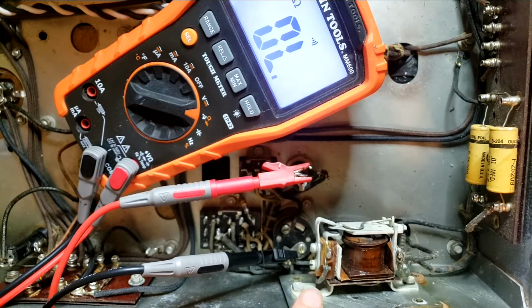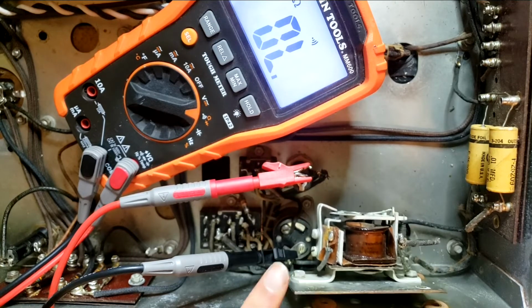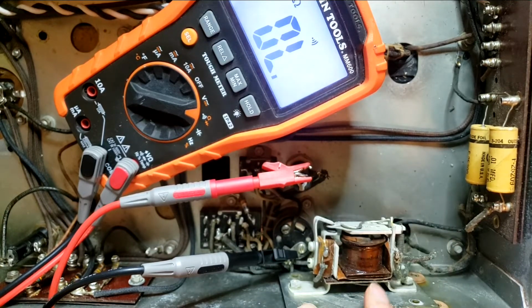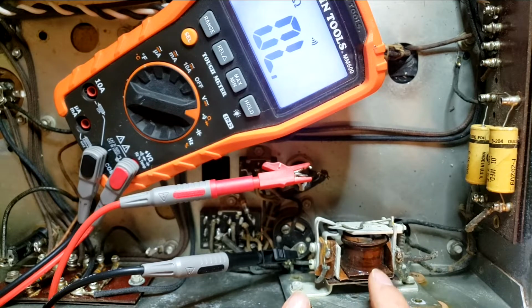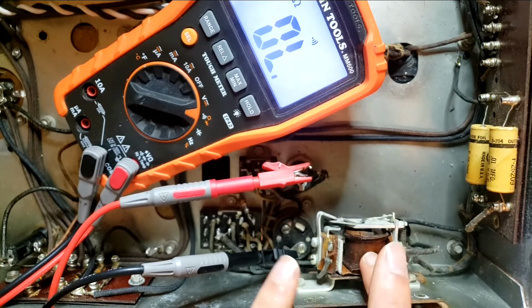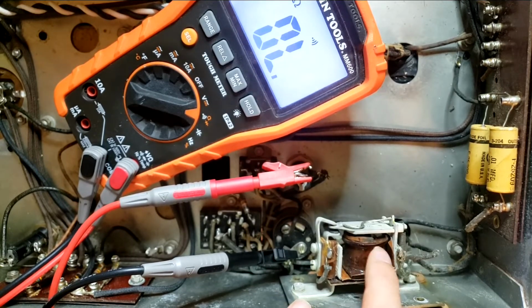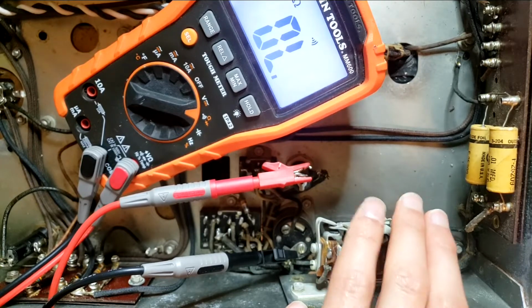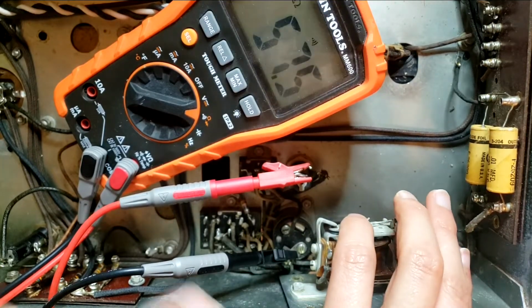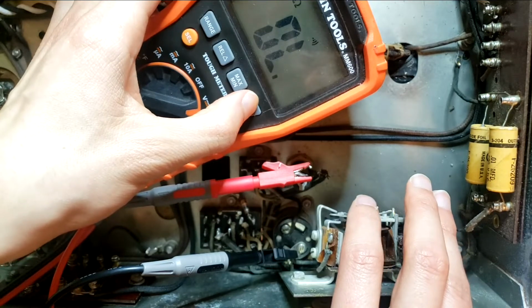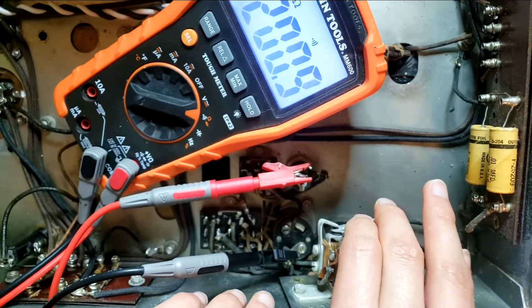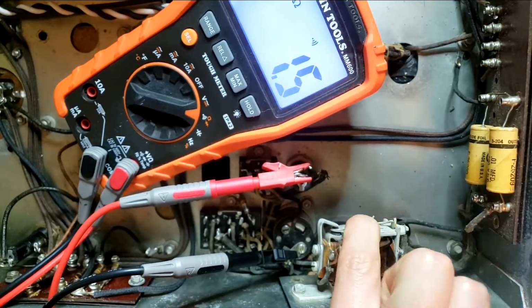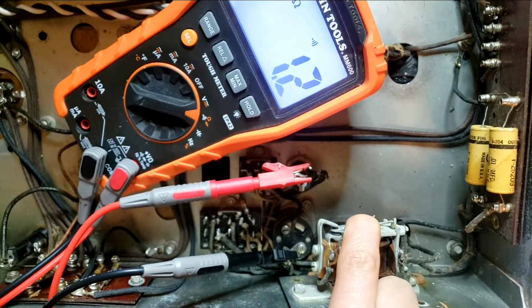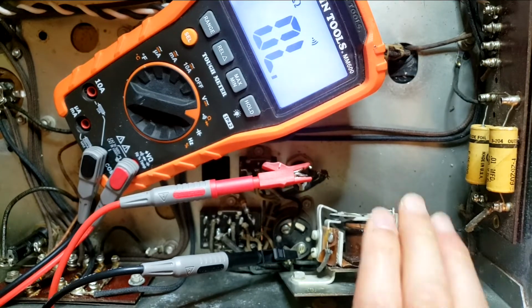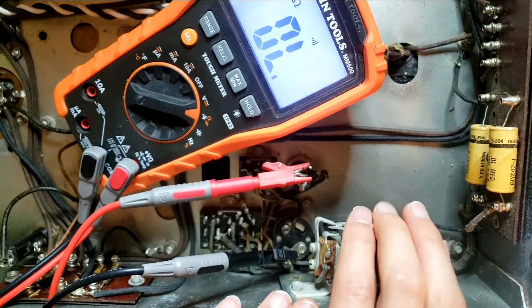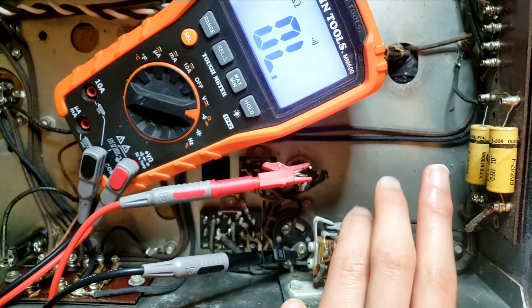In fact, this relay is the reason there's no continuity, and you'll see that. This is of course in the de-energized state because the whole amplifier is de-energized. But when I push this down to simulate the coil being energized, you can see that now we have continuity for our power input. So now the power transformer would actually be receiving power.